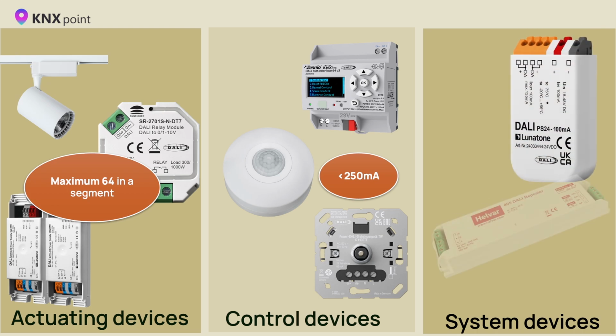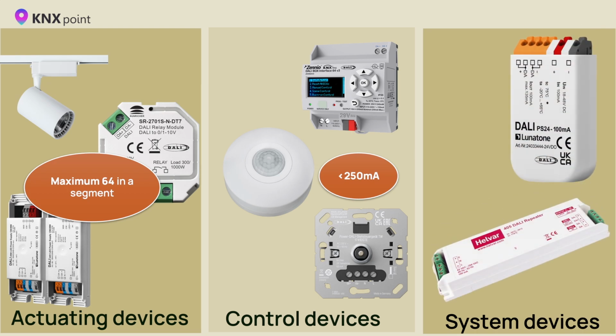System devices: gateways, amplifiers, power supplies. The power supply can be either a separate product or built into the controller. The power supply is the only DALI device for which polarity must be observed when using two or more such units simultaneously.